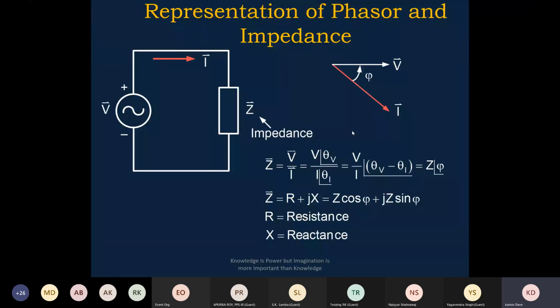See, most of the time when we do the testing of typical protection functions, like loss of excitation, pole slipping functions, df/dt functions, then line relay testing, it is more important to understand how to analyze the data. With simple voltage functions and current functions, yes, they can be easily tested with any of the test kits. So fault analysis is more important: how to interpret the data, whether the data is right or wrong, or how to convert it the other way, to match the data with expected values. That is how it has to be analyzed properly.